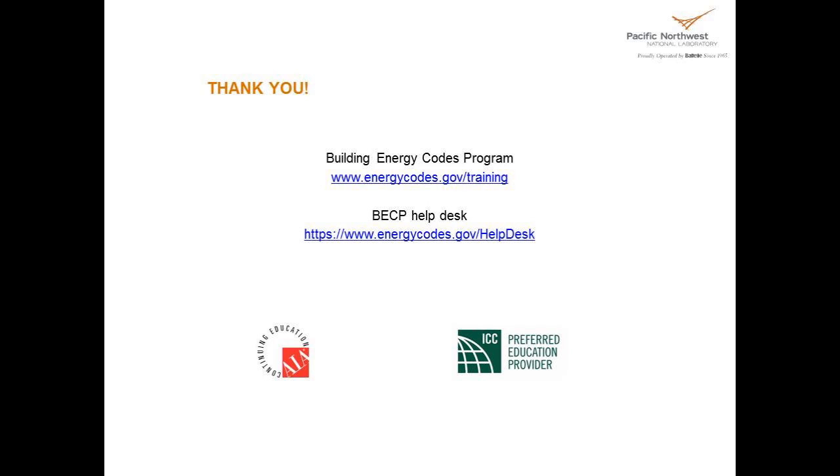Okay, that's a very good question. I probably should have spent a little bit more time on that. So what happens is, on the inside of the duct, the temperature, we'll just throw out a number, say it's 50 degrees. And if it's 80 degrees in the attic, when the duct is exposed, you essentially have 80 degrees. When you bury the duct, the surface temperature on the duct where the vapor retarder is located is going to be much colder. So it's going to be closer to the dew point, and the closer you get to the dew point, or when you pass the dew point, that's when the condensation occurs.